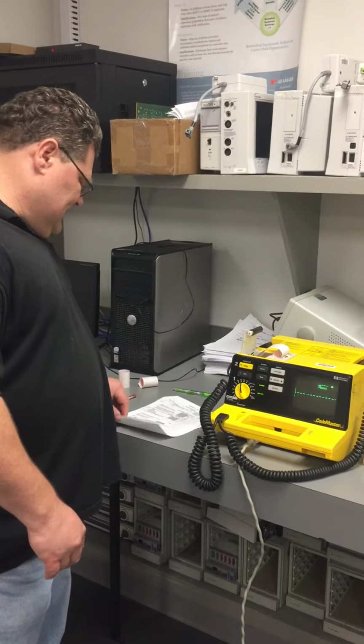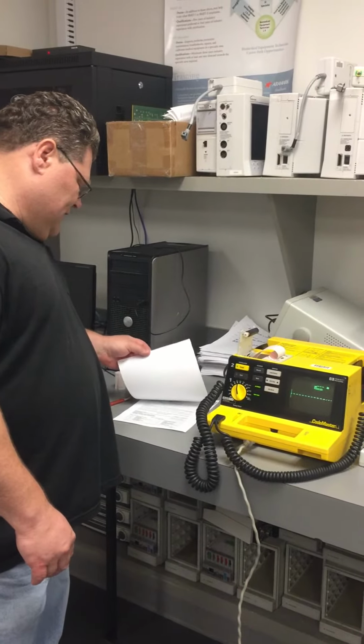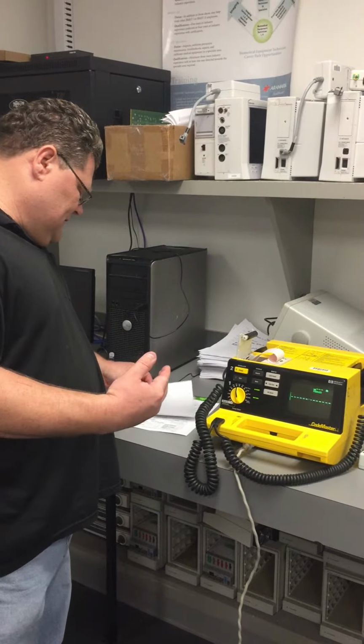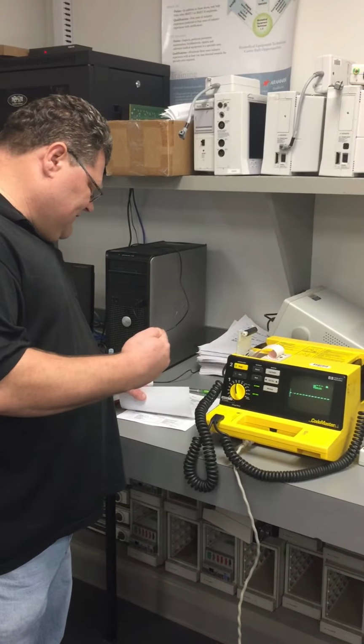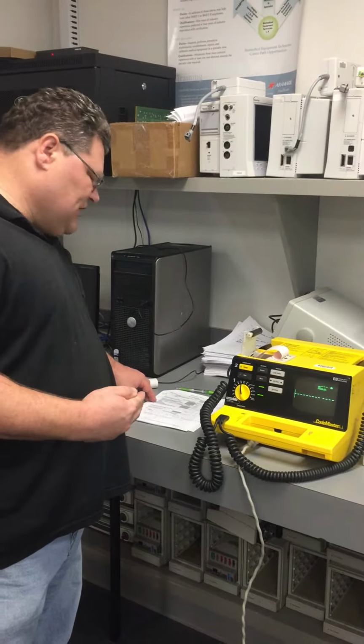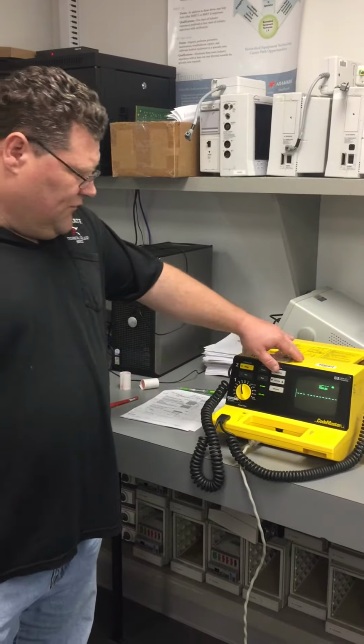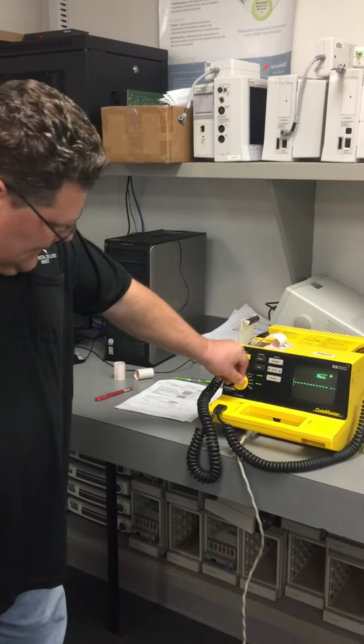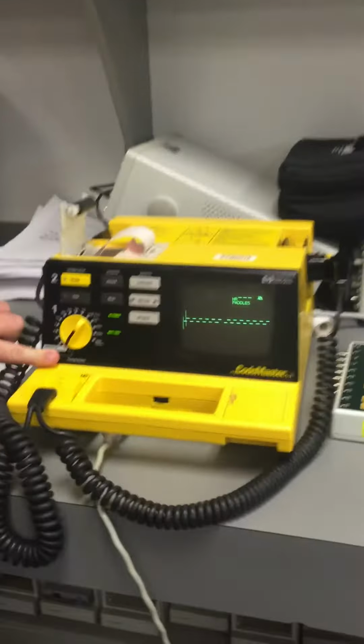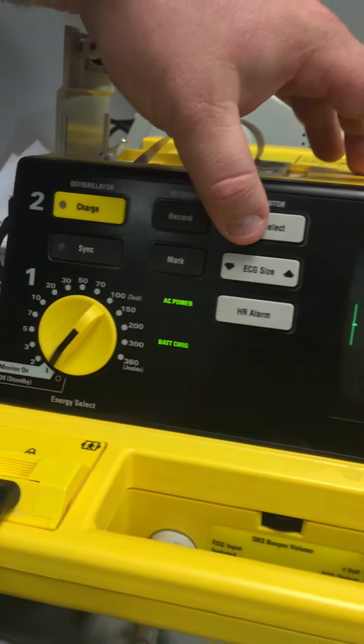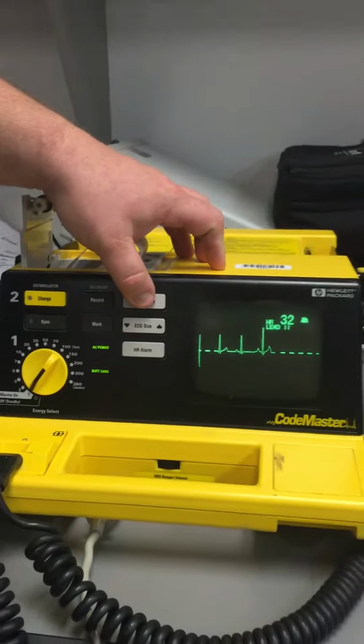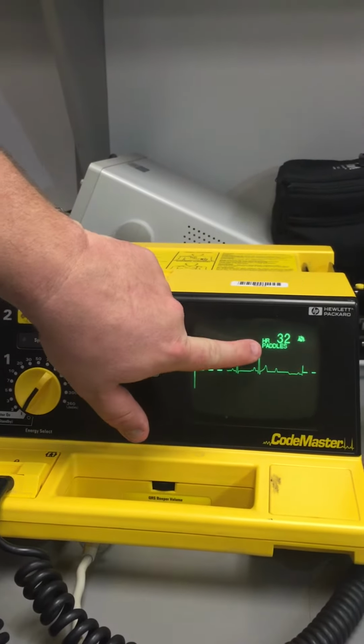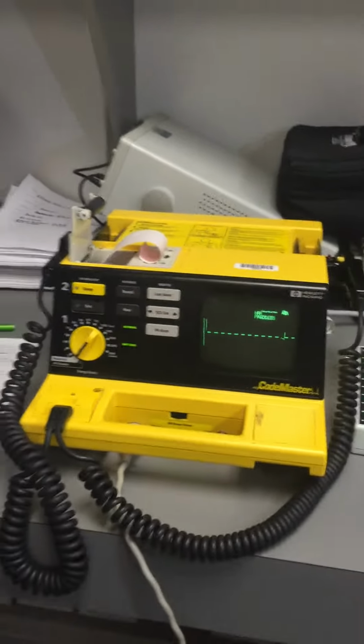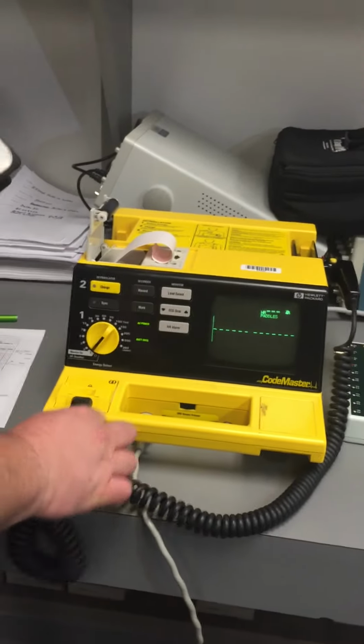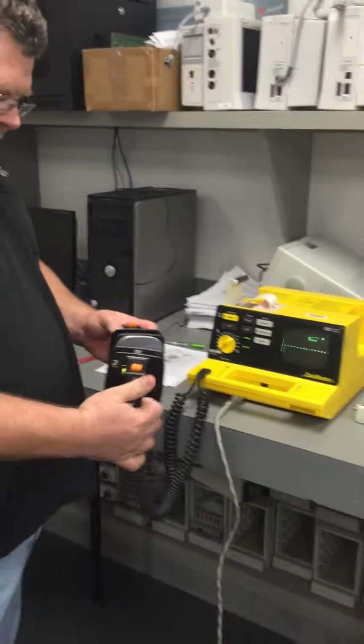Now there are a couple of things that are very handy to go through, not electrical safety, but the self-test. And I really want to start here on the paddle continuity. For a paddle continuity check, I'm going to turn it here to monitor on, and I'm going to press this lead select button until I get my leads to paddles. This is very important because what we're checking here is the continuity of the paddle. I'm going to unholster the pads.